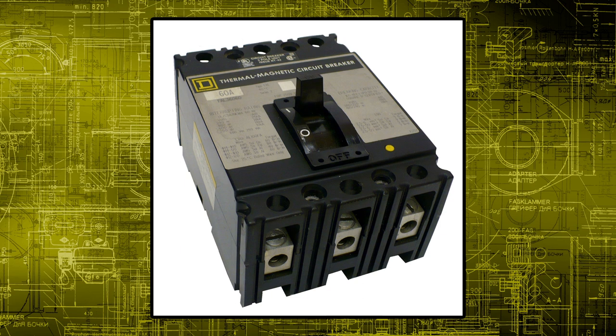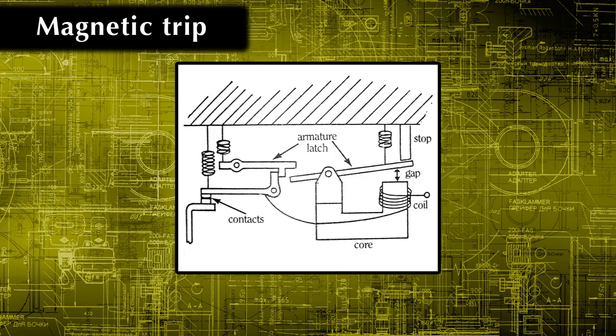It has two tripping mechanisms which are magnetic trip and thermal trip. Magnetic trip deals with short circuits. It consists of an iron core with a wire wrapped around it. Load current flows in the wire and thus generates a magnetic field. When short circuit current occurs, this magnetic field becomes powerful and will attract a nearby armature which in turn trips the circuit.